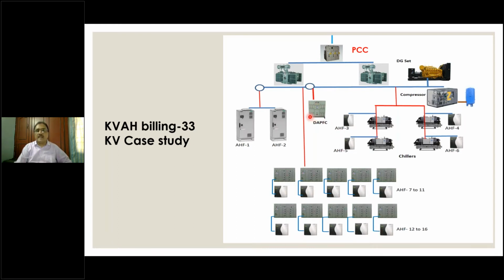This facility already had a detuned APFC. So we did not look at the amplification as a problem. There was no amplification, but the harmonic content was very high in each of these equipments. Chinese equipments and heavy harmonic was there, and they were also affecting parallel branch circuits. And they had huge failures of PCB boards. They were spending almost 1 crore for PCB boards replacement or repair or whatever. That was the kind of situation in which they invited us, and we found that the harmonic is causing the problem. Harmonic is not getting amplified because any amplified harmonic will flow towards the grid. That was not the problem.